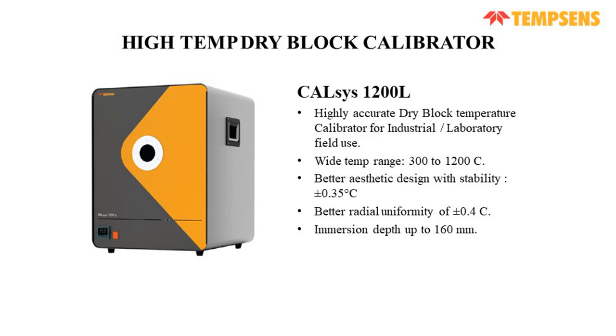Next, we have the high temperature dry block calibrators. It is for laboratory purpose. The weight of these models will be around 50 to 55 kgs, but these can be placed at a place, for laboratory or industrial calibration. So 1200L has a block, and the block similarly has holes for the RTDs and thermocouples. The temperature range for this model is 300 to 1200 degrees centigrade, and it has a stability of plus minus 0.35 degrees centigrade. It has very good uniformity of plus minus 0.4 degrees centigrade, and an immersion depth up to 160 mm.